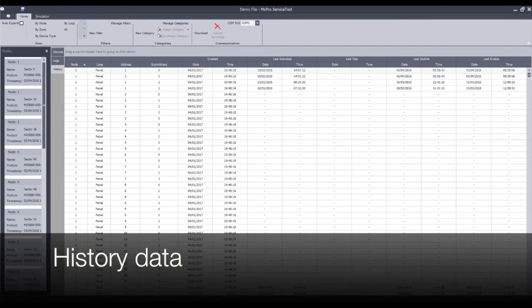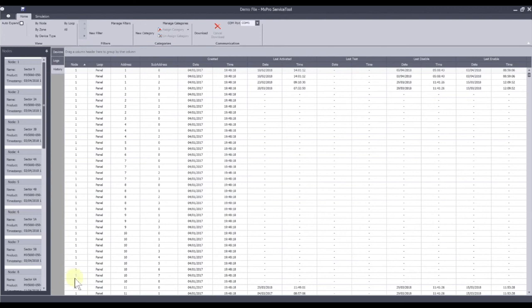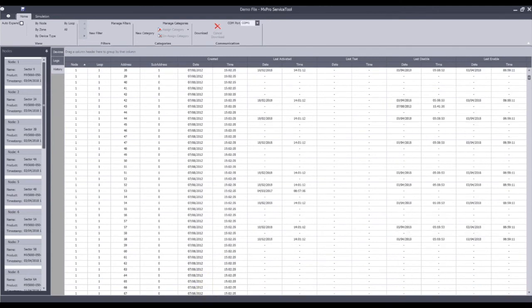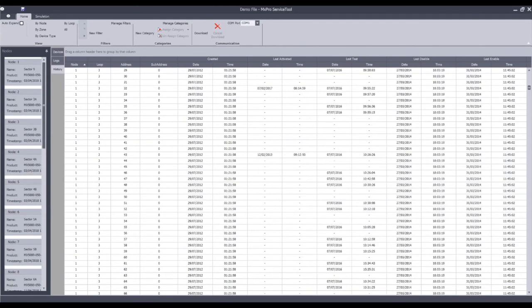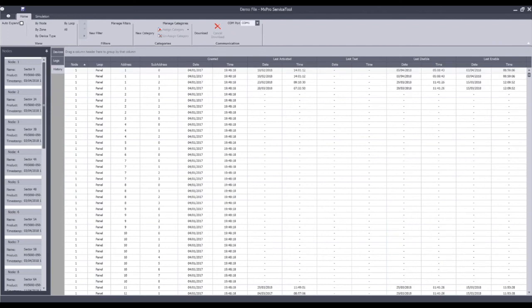The history data allows you to see when a device was actually added to a system. In this example, Node 1, Loop 1, Address 1 was added on the 4th of January 2017 at 19:48. The last activation — activation being a fire alarm or a real fire scenario, or a walk test in real fire rather than single one-man walk test mode — was the 18th of February 2018 at 14:01. The last test column corresponds to the one-man walk test. Scrolling down, significant if not all devices have not been tested in a walk test scenario; however, they have been tested in fire alarm, so we know that the system does work. It also covers the last time the devices were disabled and the last time the devices were enabled, so you can see the history of when a device was isolated.